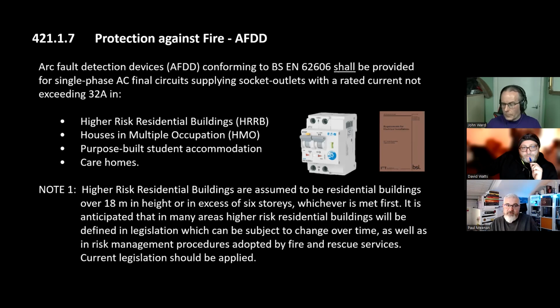So this is what the new reg says. AFDD conforming to 62606 shall be provided for single phase up to 32 amp. And then it says in high-rise residential buildings, houses in multiple occupation, purpose-built student accommodation and care homes. For me, far more succinct, far more sensible. It's a good start. It is a very good start.